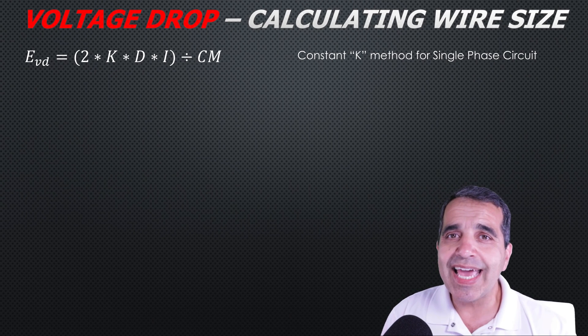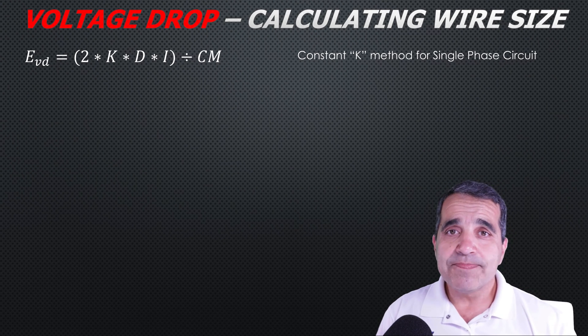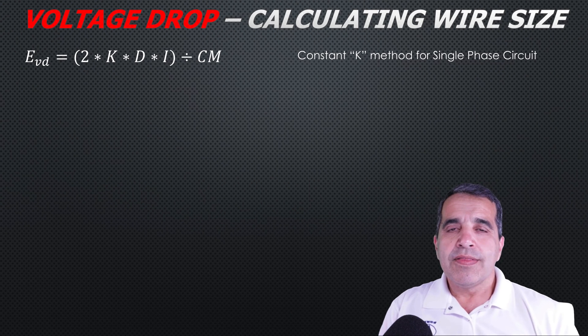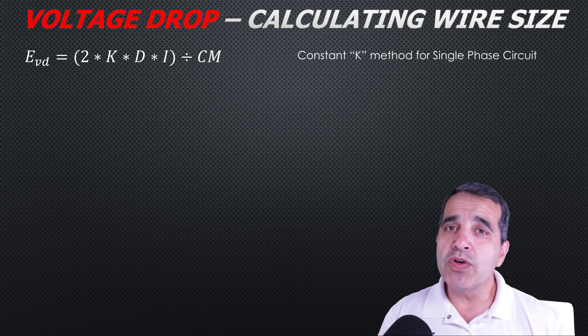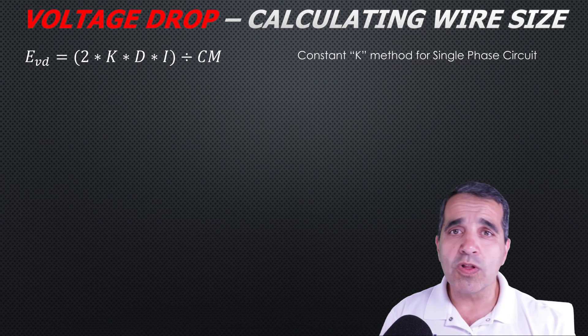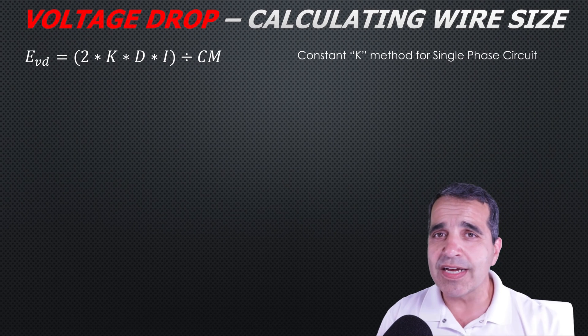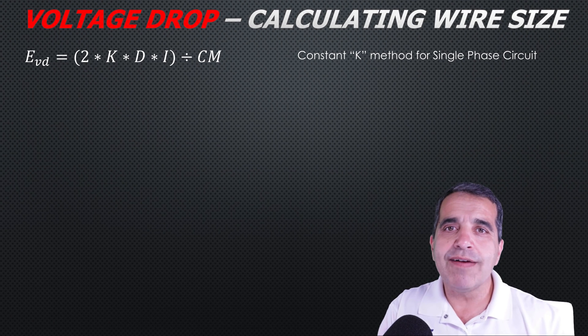I'll explain what K is and where you get it. If you search for K in the National Electric Code, you won't find it — it's a constant value based on the circular mils of a conductor per thousand feet, and you have to extrapolate it from the code. On a single-phase circuit, you multiply two times the constant K for copper or aluminum, times the one-way distance of the conductor, times the amperage of the branch circuit.